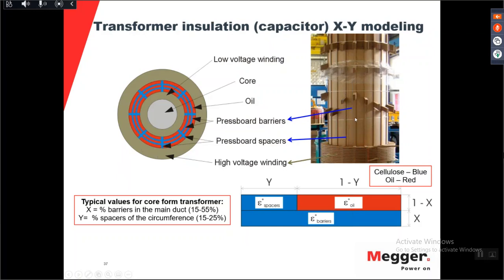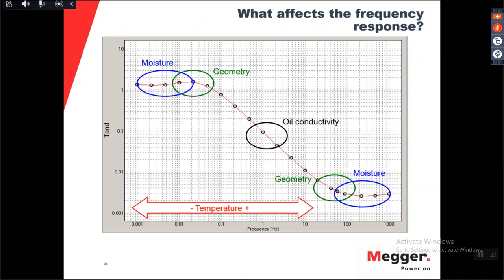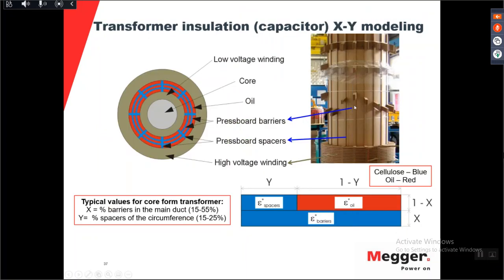Can you see these boards here going straight along the surface here? Here's one, here's one, here's one. And then you have a big paper cylinder going around here. This is this one here. Then, depending on the size of the transformer, you can have 2 or 3 or 4 different paper cylinders and so on. Why is the transformer constructed like this? Because here you have an empty space, and when you fill the transformer with oil, this will of course be filled with oil.